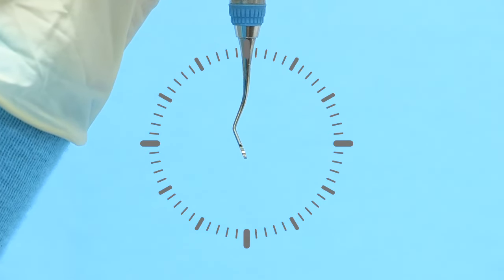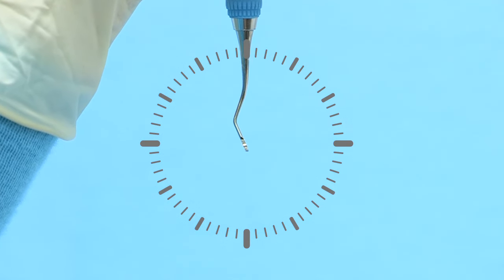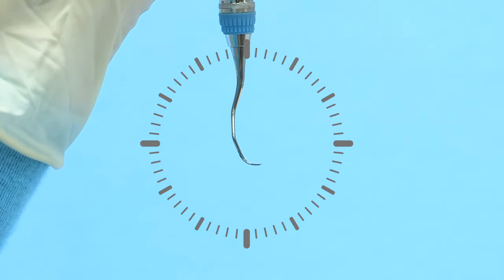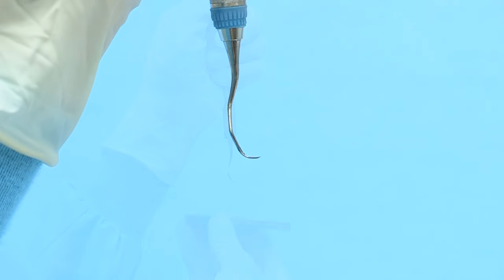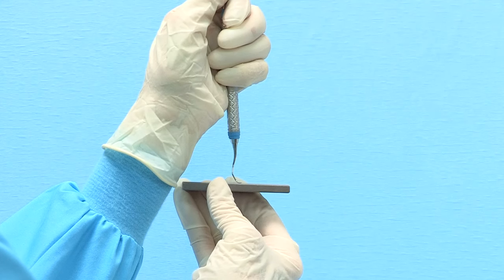To round the toe of the odd-numbered Gracey Curette, maintain the terminal shank at three minutes before 12 o'clock. Slowly rotate the instrument handle so that the toe is directed at the three o'clock position. The face of the instrument should be parallel to the table surface. Position the stone at three o'clock and tilt the stone upward to the two o'clock position. Move the stone in a consistent motion overlapping the strokes and rotating around the toe to maintain the rounded shape.